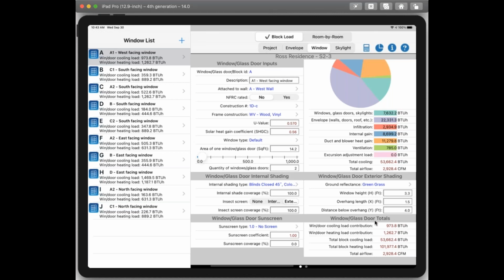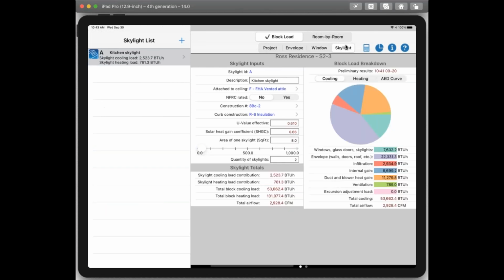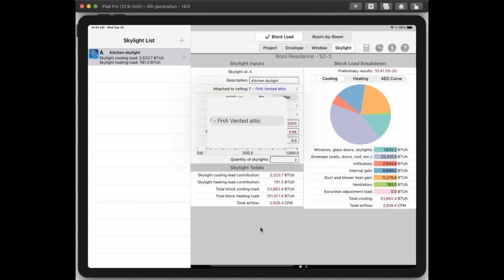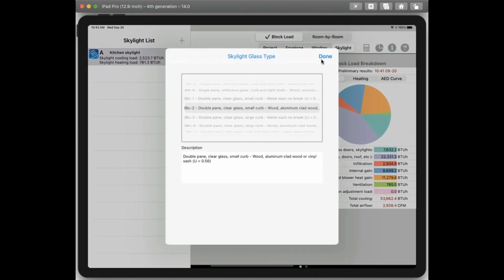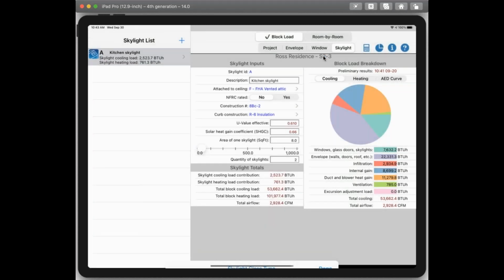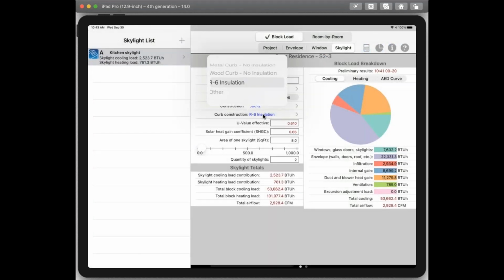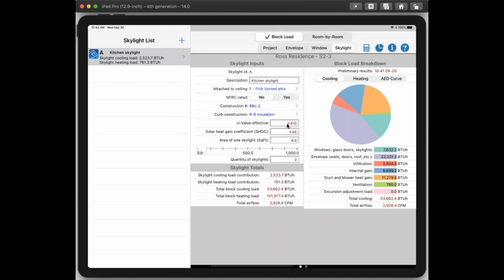All right, so let's move on to Skylight. Skylight's pretty simple. Once again, you can add as many skylights as you want. Here I just have 1 skylight. It's in my kitchen. I assign it to the ceiling, which I defined under my envelope. And then I can select the construction type for my skylight, single, double, or triple pane. What type of curb construction does my skylight have? Based upon these 2 inputs, it will automatically fill in my U value and my solar heat gain coefficient. I enter the area of one skylight if I have one. If I have multiple ones, I can enter the quantity here, and then it will calculate my skylight load.